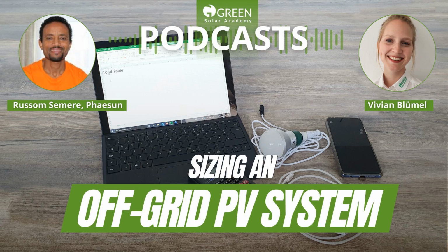And then the battery is also important to consider with the energy consumption, so how much energy is being produced per day. All this should be stored in this battery. And also very important is the autonomy days. Autonomy days is how many days you have in a year where there is no sun. Sometimes it can be a rainy day, sometimes a cloudy day. During these cloudy or rainy days, the battery should be able to deliver the required energy to the loads.